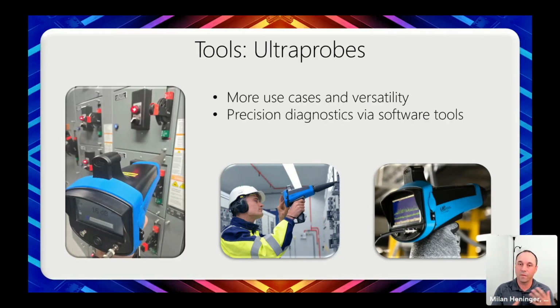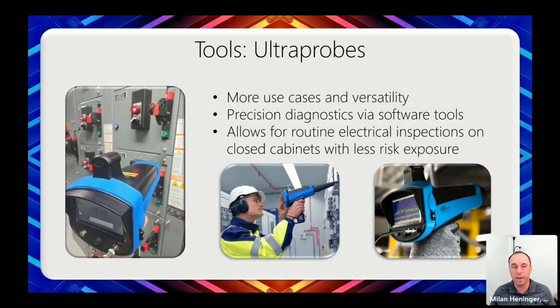In cases where you have competing ultrasound or a more complex situation, I've found it's easier to do the diagnostics using the software tools that are usually used, so Spectralizer in this case. Finally, it allows for routine electrical inspections on closed cabinets with a lot less risk exposure. By scanning around the gaps of the doors, you're able to pick up ultrasound due to some properties of ultrasound, and it allows you to do some pretty precise diagnostics.